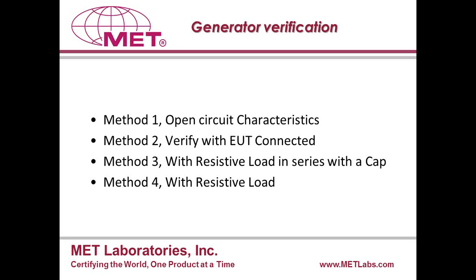The final method, method 4, is more appealing, where the standard says to use resistive loads, and the standard specifies a table. In a nutshell, the idea is to use a resistive load comparable to the steady state current drawn by the EUT, and using that method validate the rise time, fall time, and duration. The standard says in addition to that also provide the actual waveforms when the EUT is hooked up with the generator. So it's a little bit extra work, but this is the most practical, meaningful method of validating the test generator.